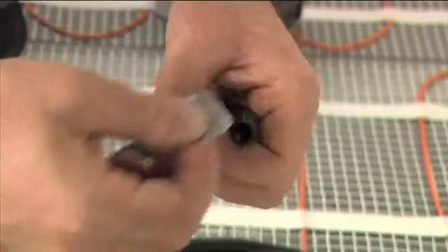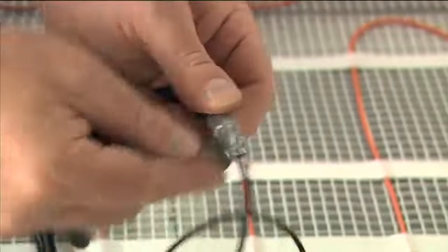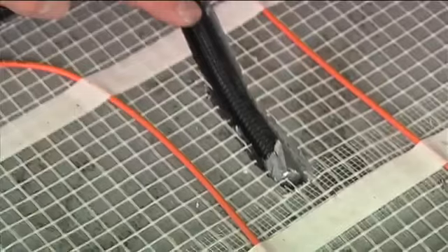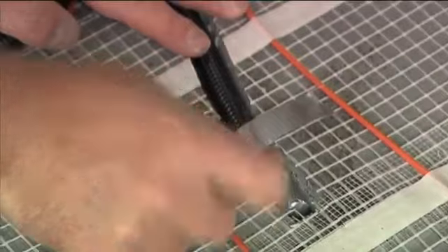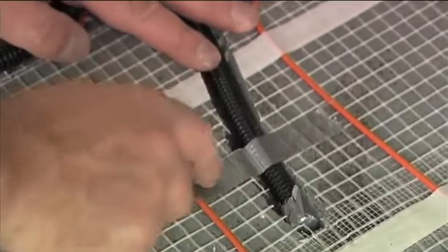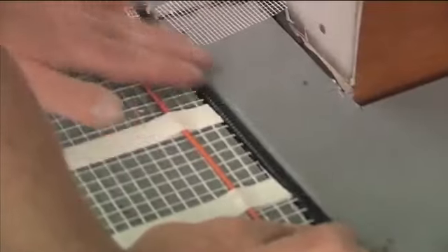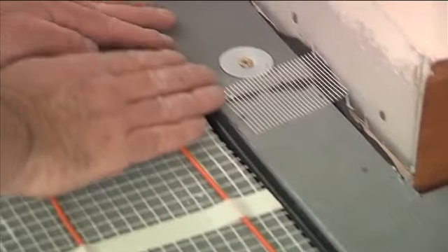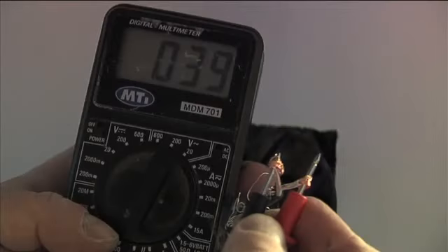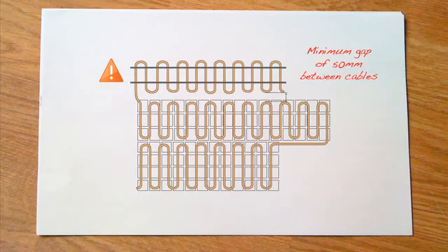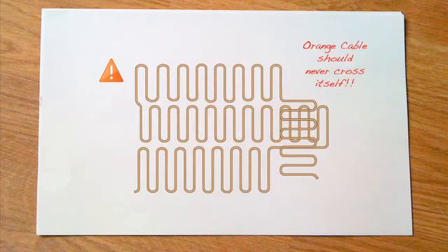Insert the floor limit sensor into the protective conduit and recess into the subfloor. The sensor should be positioned between two cable loops. Tape the end of the conduit to prevent ingress of the tile adhesive. Once again, check the cable resistance against the label value to ensure it has not been damaged. When the cable is removed from the matting, always maintain a minimum 50 mm gap between cables. The orange heating cables should never cross.